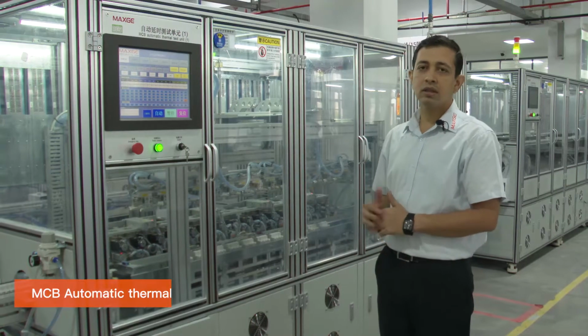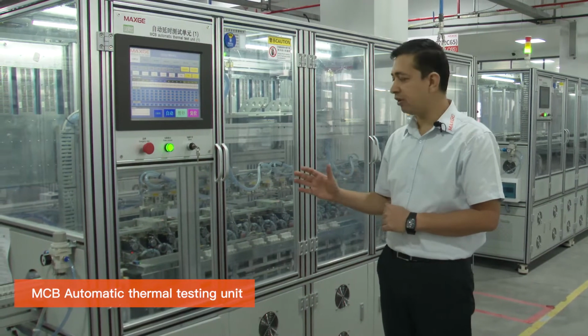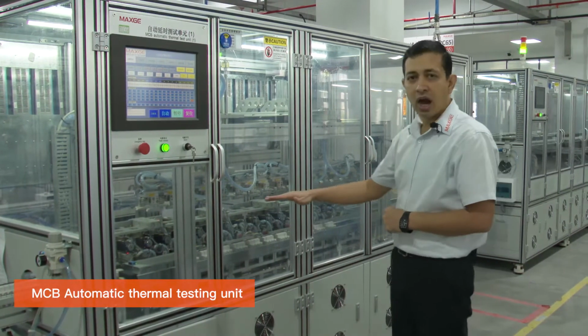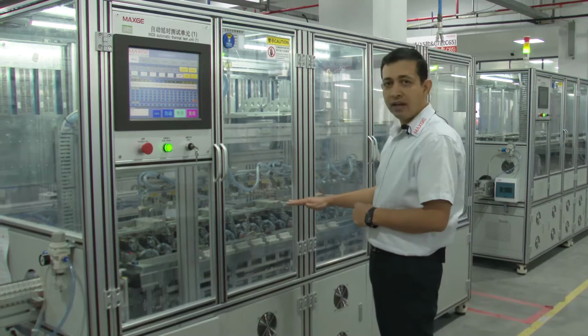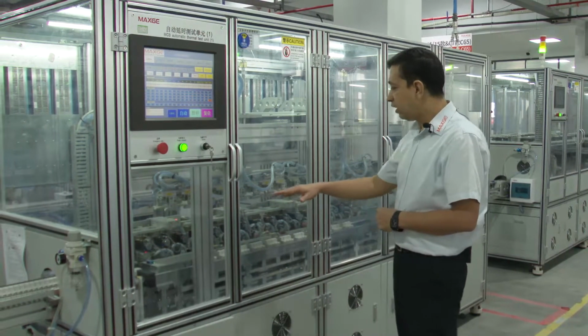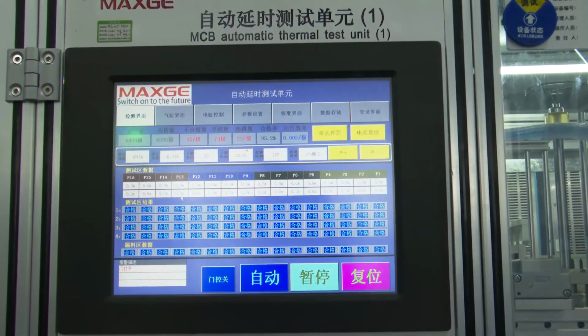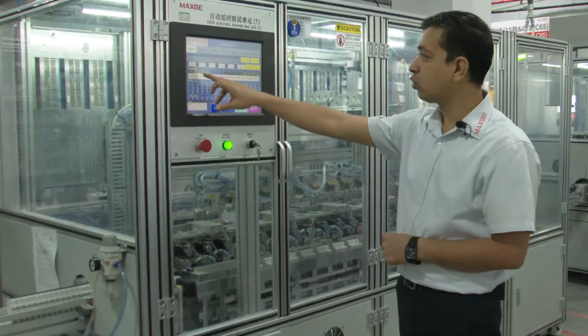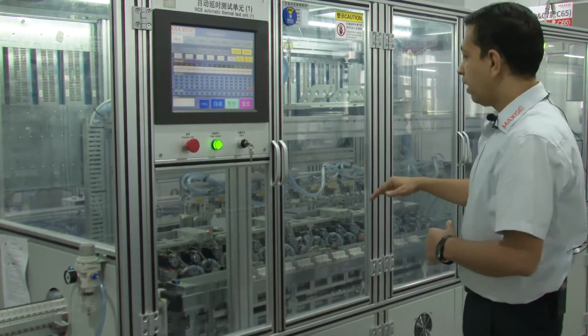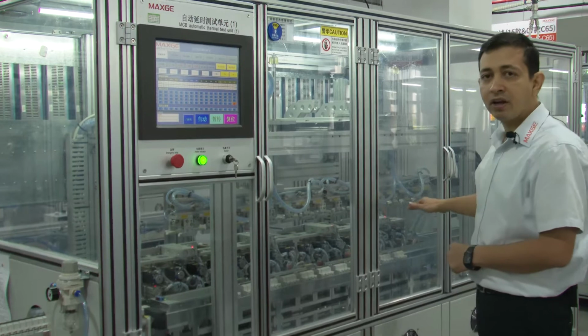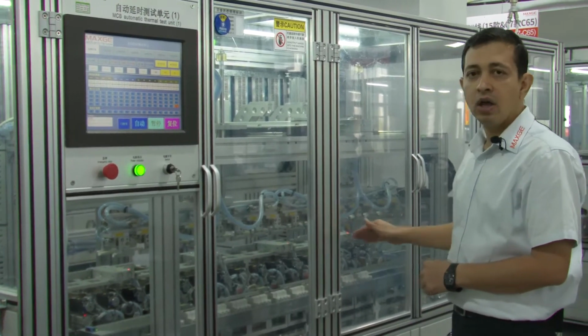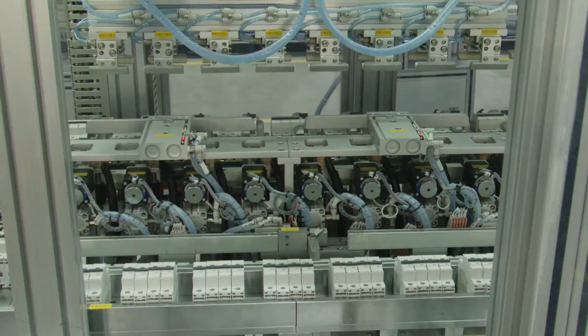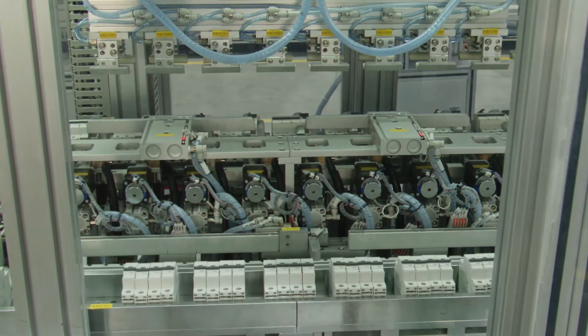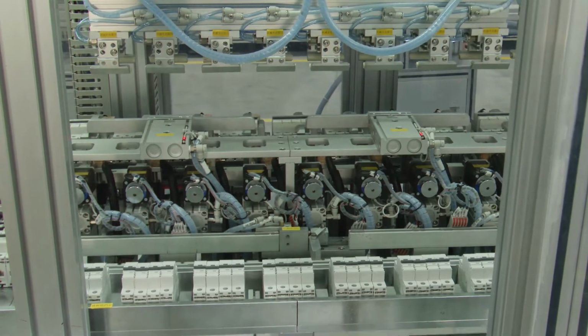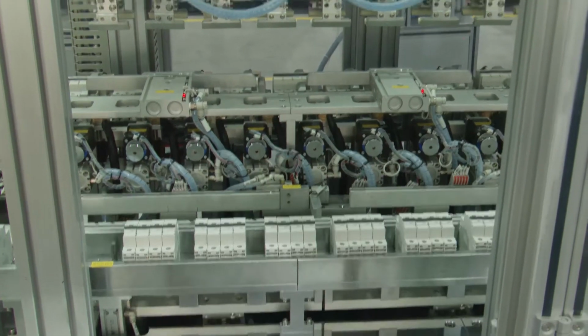Now we are at the automatic thermal calibration machine. This is the real heart of the testing line. You can see there are a total of 16 workstations. At a time 16 breakers are being hot calibrated. So what does hot calibration mean? Normally there are two types of calibration for the MCB. One is the hot and one is the cold calibration.